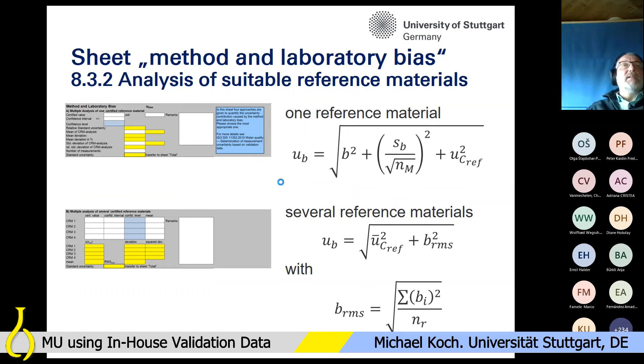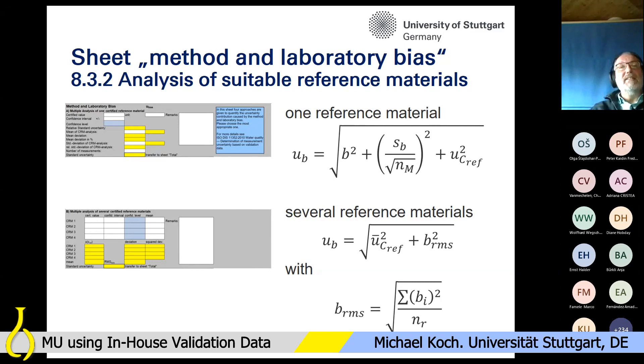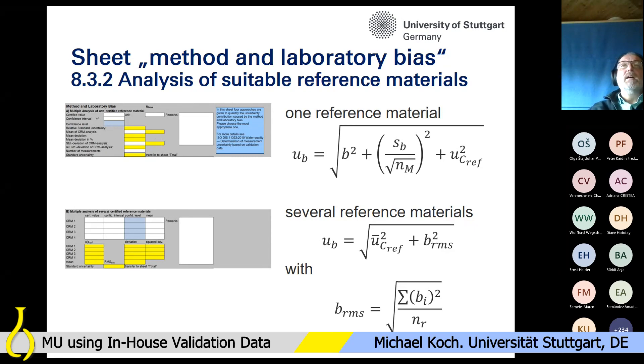The formulas in the yellow fields are exactly taken from ISO 11352. Coming back to the validation issue that was just discussed: this software also comes without any guarantee and without any validation document. But it's very easy to validate — the only thing you have to do is check whether the formulas in the yellow cells are the same formulas as in the ISO standard, and that's it.